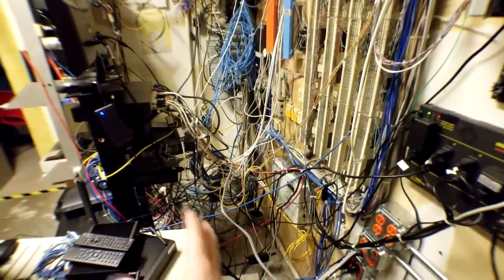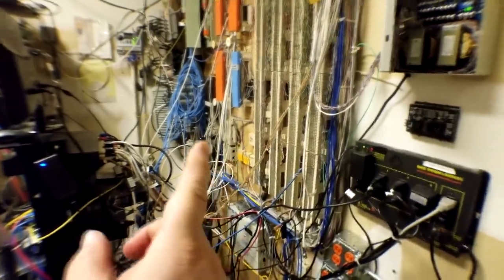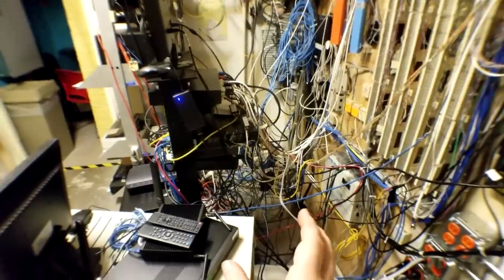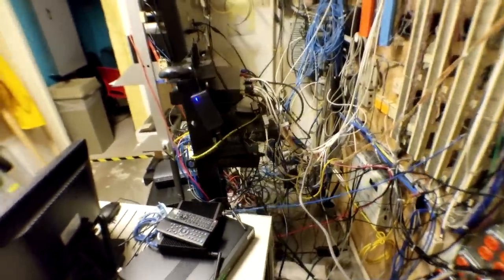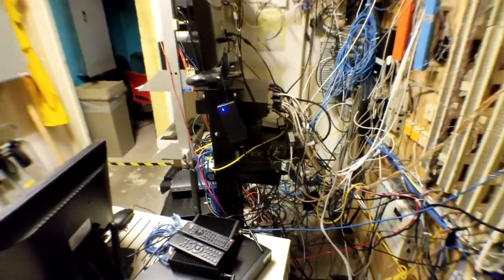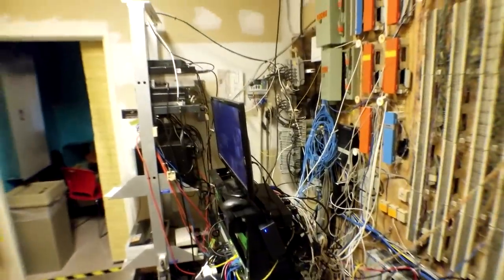This is the issue that makes this site absolutely untouchable. By draping all these lines along the floor, you've basically blocked access to the back and to the backboards, which is very important not only to you but to outside vendors like cable and fiber providers. Phone company technicians are going to say no — they would potentially damage everything in front. We have limited time and resources, so we're figuring out what we can do without completely gutting the room. The center rack is most likely going to get pulled out and replaced.